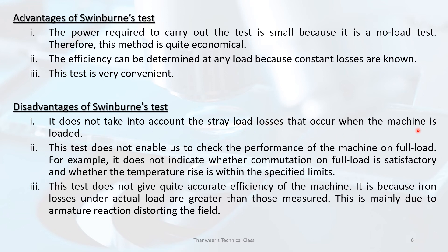This test is very convenient. The disadvantages are: it does not take into account the stray load losses that occur when the machine is loaded. This test does not enable us to check the performance of the machine on full load — for example, it does not indicate whether commutation on full load is satisfactory or whether the temperature rise is within the specified limit.